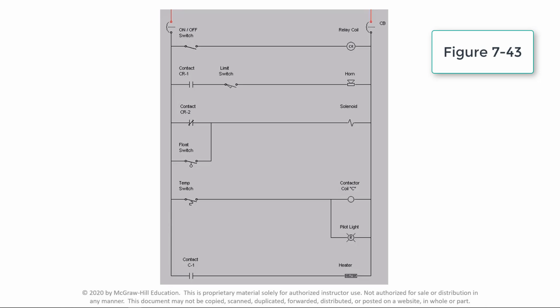When the temperature switch closes, the contactor coil energizes and acts to close the C1 contact. At the same time, the circuit is completed to the red pilot light, switching it on. The heater unit is energized and operates whenever contact C1 is closed.